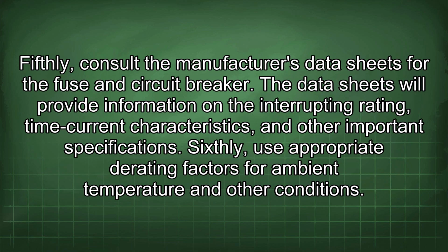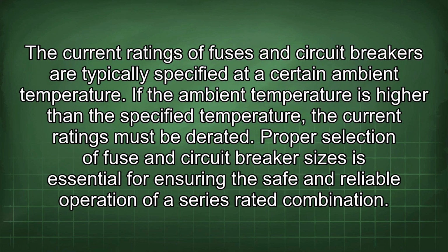Fifthly, consult the manufacturer's data sheets for the fuse and circuit breaker. The data sheets will provide information on the interrupting rating, time current characteristics, and other important specifications. Sixthly, use appropriate derating factors for ambient temperature and other conditions. The current ratings of fuses and circuit breakers are typically specified at a certain ambient temperature. If the ambient temperature is higher than the specified temperature, the current ratings must be derated.